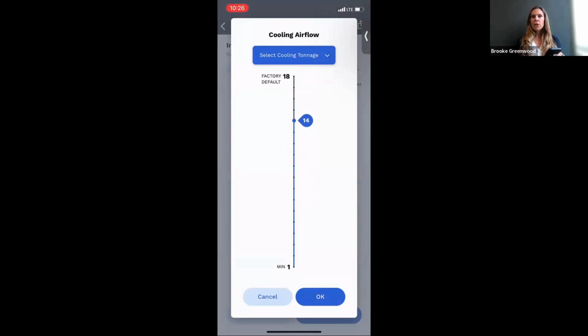Now, one thing we've done to try to build efficiencies into the app and give some direction from a configuration and airflow perspective: you see at the top it says select cooling tonnage. This is a drop-down box, and if you're pairing this with a certain tonnage outdoor system, you've got lots of options here, not just 1 or 2 like you might have had in the past with your 5-speed product. If I'm matching this with a 3-ton outdoor unit, I make that selection, and it knows that airflow speed range recommended is 350 CFM per ton at 0.5 static to 400 CFM per ton at 0.8 static.